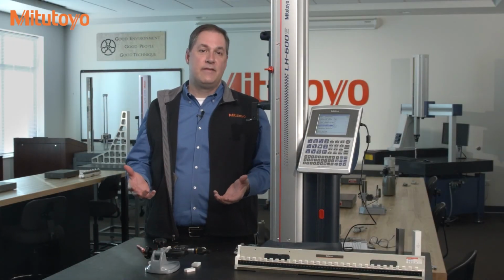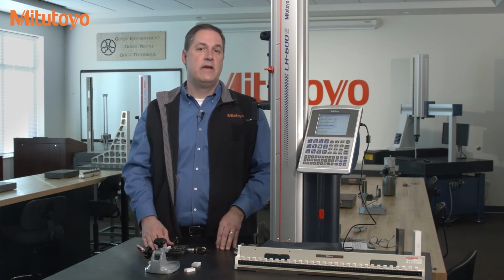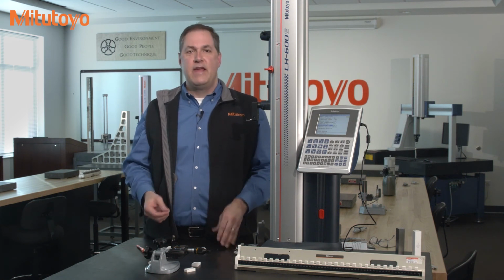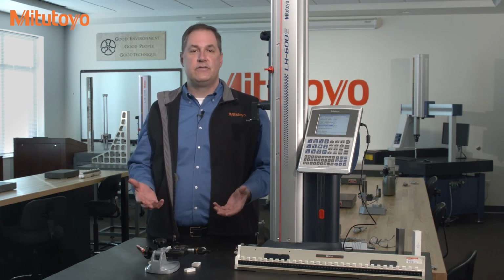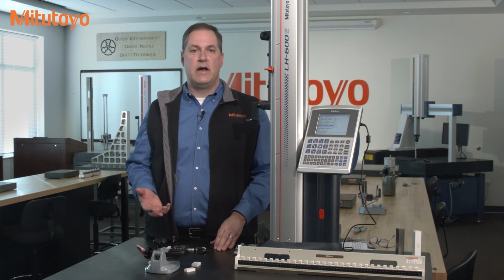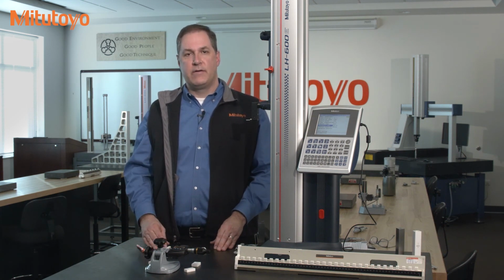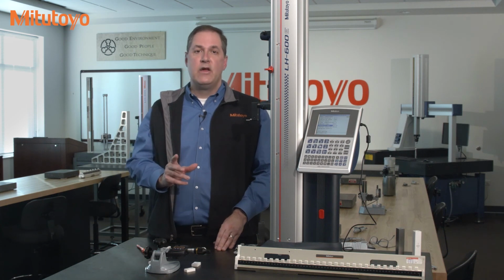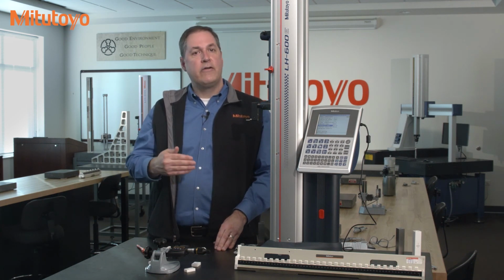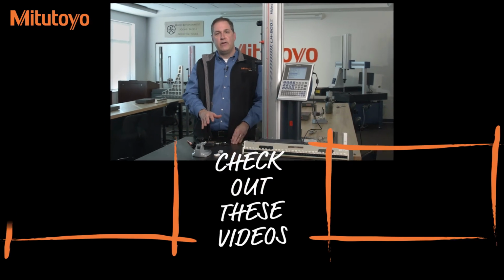Now, I can't promise this will work for you. Our calibration history of our gauge blocks support this method, and so we're comfortable with it. If you don't want to mess with worrying about these issues, just get some grade 00 gauge blocks for calibrating your MDH micrometer. And one last thing, when you start calibrating more accurate instruments, like an MDH micrometer, you may need to look for a new calibration provider for your gauge blocks who can provide better measurement uncertainty. Be careful with that. All right, that's everything for this episode.